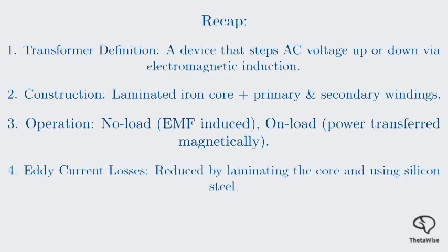We discussed how eddy current losses are reduced by laminating the core and using silicon steel. And finally, we detailed the various cooling methods, from natural air to oil-immersed water cooling, and the vital components like the conservator tank, breather, and Buchholz relay. Understanding these principles is crucial for working with transformers in any electrical system.